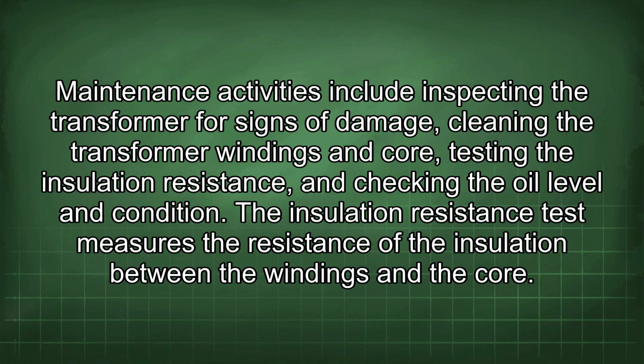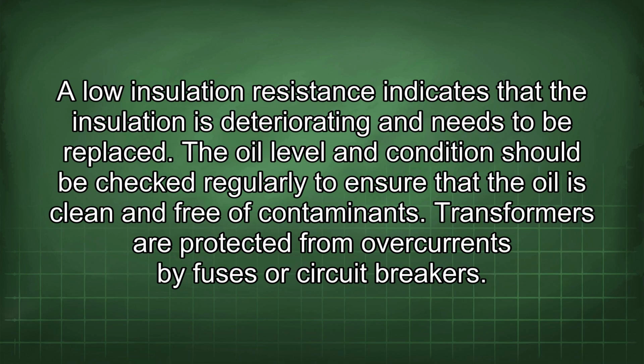The insulation resistance test measures the resistance of the insulation between the windings and the core. A low insulation resistance indicates that the insulation is deteriorating and needs to be replaced. The oil level and condition should be checked regularly to ensure that the oil is clean and free of contaminants.